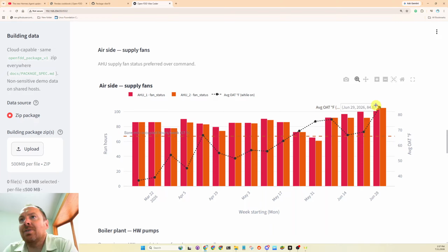We talked about this earlier too, like you can kind of see in the data it drops off, which is somewhat typical to shoulder season. That's when we should absolutely be running the air handling unit bare minimum, when we're in this 50 to 60 degree outside air temperature range. In theory, you wouldn't need to heat the building, so we only run the air handling unit for ventilation purposes only.